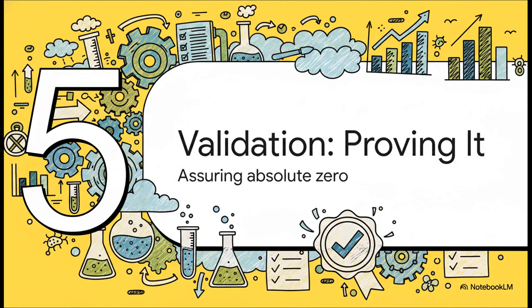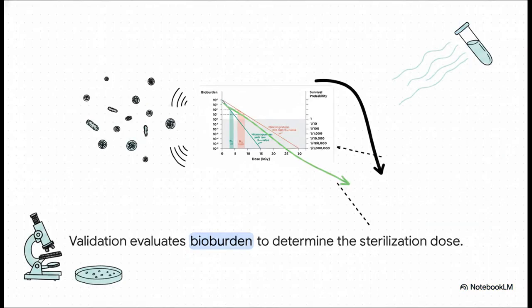All right, all of this high-tech science brings us to our final stop, Section 5, validation. Proving it works and assuring we actually hit absolute zero. You see, to actually guarantee your safety, scientists first have to evaluate something called the bioburden. That's just the natural starting number of microorganisms already chilling on the product. By plotting this initial microscopic head count against the known radiation resistance of those specific microbes, they can draw out this precise graph you're seeing. It tells them exactly how high the radiation dose or the heat cycle has to be to push the survival probability all the way down to that crazy 1 in a million standard. They are literally mapping out the mathematical death of the bacteria.